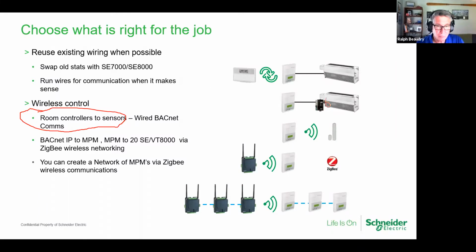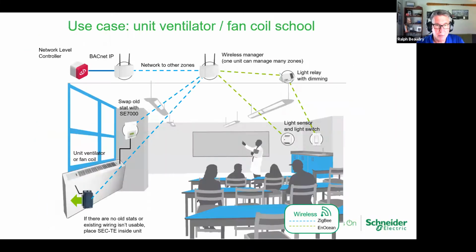That's where wireless communication makes sense. I've got a couple of quick use cases here. This is like a typical school application I see often. You've got a unit ventilator on the outside wall. We know that's not the best place for a thermostat, but it's inexpensive to hard connect a thermostat right there at the unit vent. So I could do that and put a wireless sensor across the room to get temperature sensing in the optimal spot, communicating back to my SE8000.